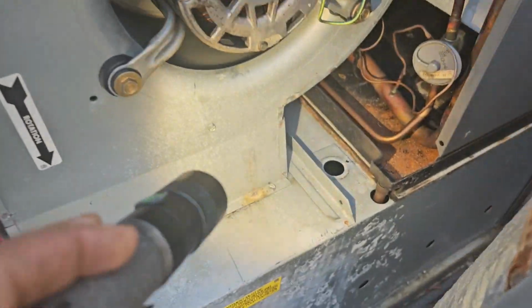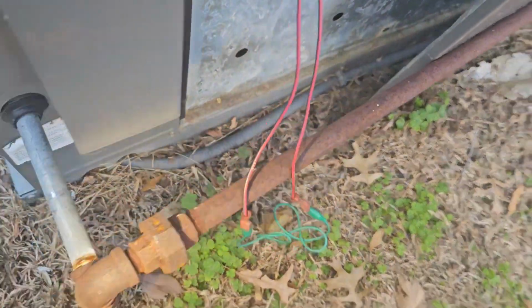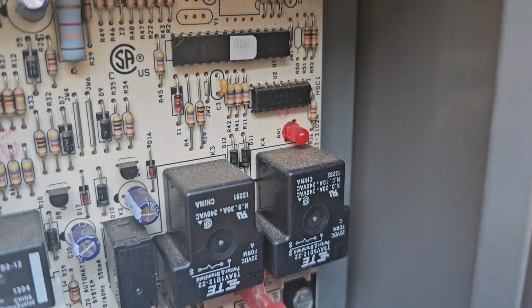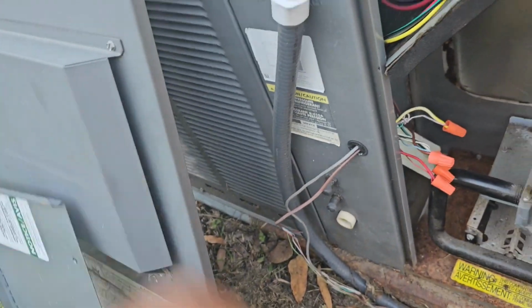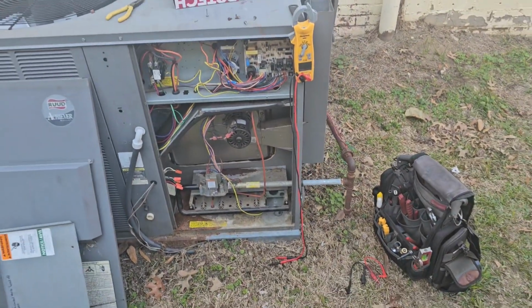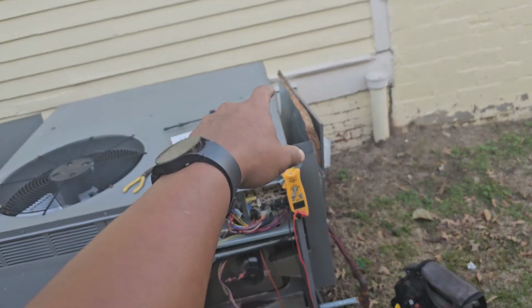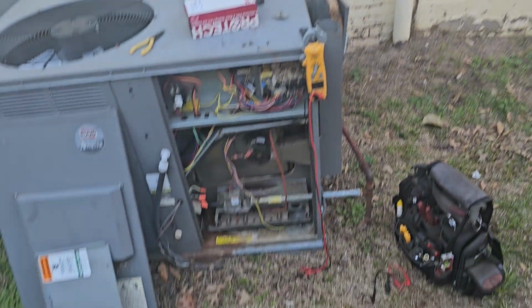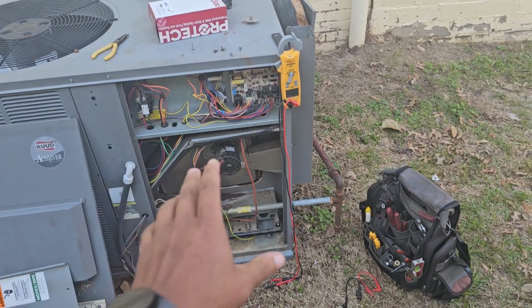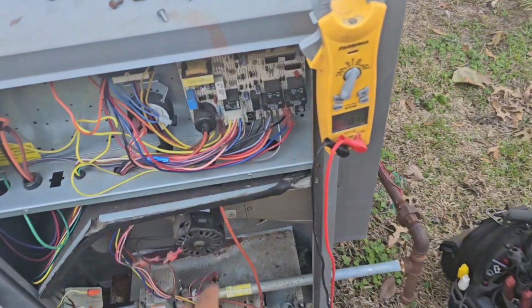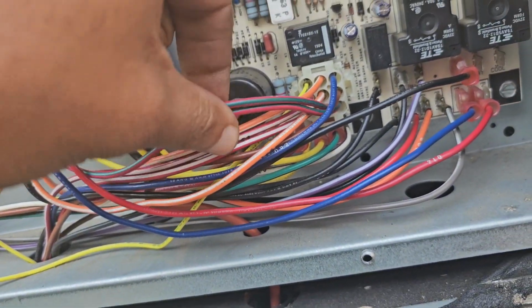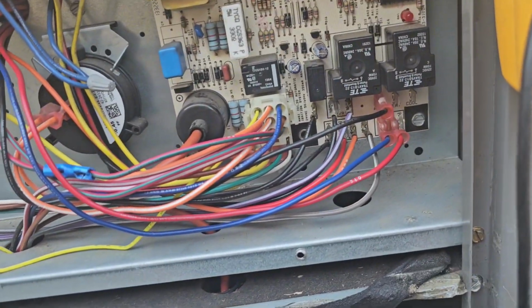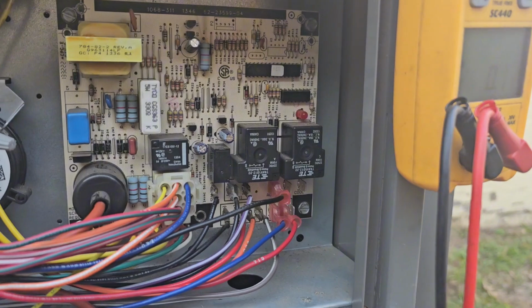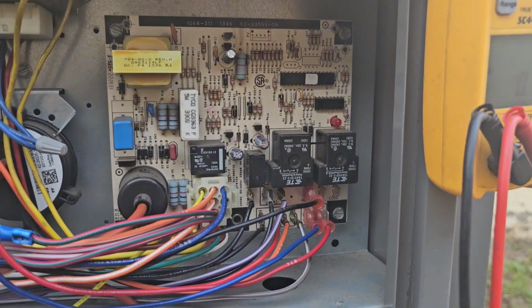Also have the blower door off, limit switch removed. It's sitting right here, I have it bypassed, and the board is still throwing the 1-2-3 flash code for the high limit switch protection device. So I was really about to kick myself, but I do think it's the board. I think when I reset it, pulling the disconnect out and putting it back in, that probably reset the whole thing. But just sitting here watching it, I've tested it. I still have 24 volts to ground from each of these red and green wires to this back plate, I get 26 volts, and across them I'm getting 0. So I'm definitely going to change this board out and not feel like a complete tool.